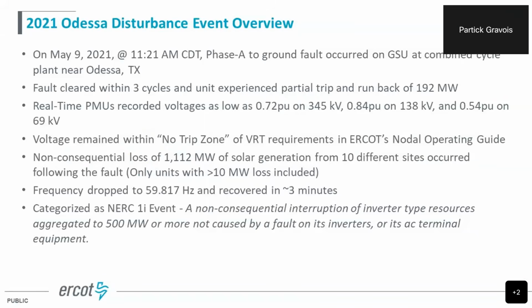All right, so we'll start with the first event and do an overview, go through the analysis and some of the things that were done since that event, and then lead into the second event in 2022. So the first event occurred May 9th of 2021 at 11:21 a.m., where there was a single line to ground fault on a generator step-up transformer at a combined cycle plant right around Odessa, Texas. It was a normally cleared fault, cleared in about 3 cycles. The combined cycle plant experienced a partial trip and a run back of roughly 200 megawatts.